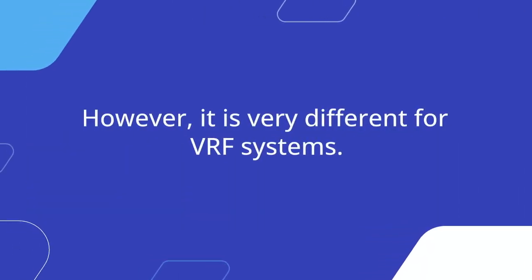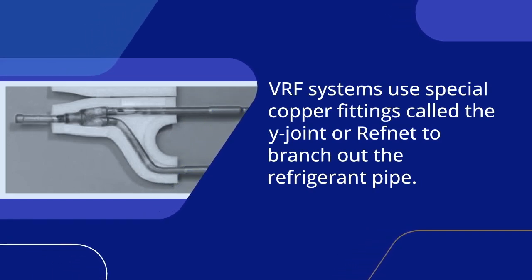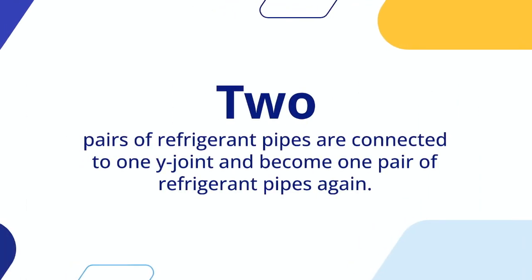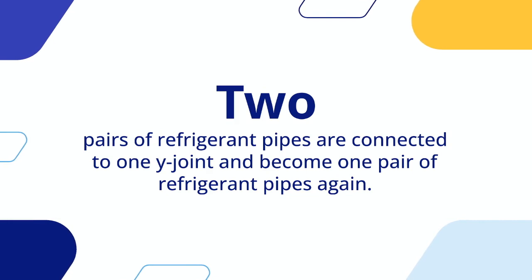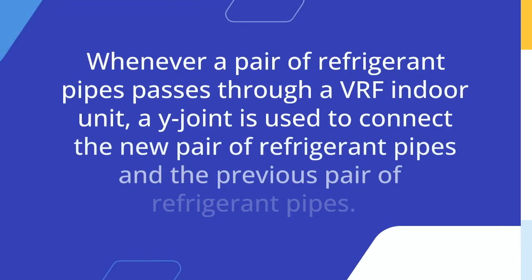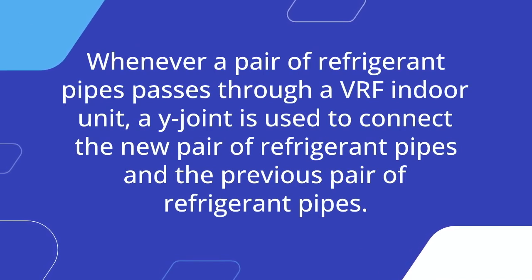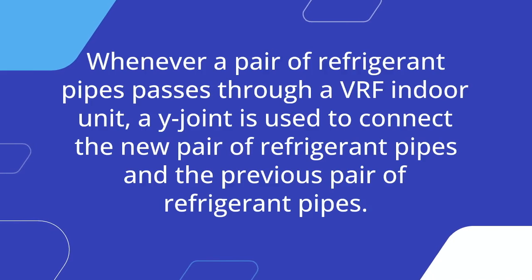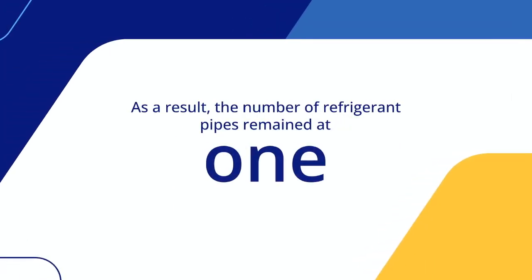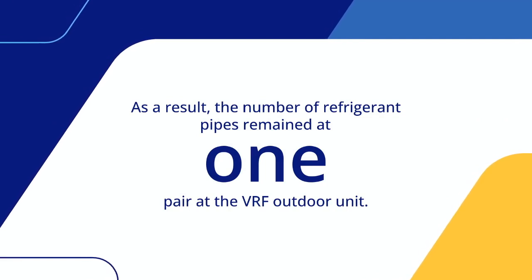It is very different for VRF systems. VRF systems use special copper fittings called the Y-joint or refnet to branch out the refrigerant pipe. Two pairs of refrigerant pipes are connected to one Y-joint and become one pair of refrigerant pipes again. Whenever a pair of refrigerant pipes passes through a VRF indoor unit, a Y-joint is used to connect the new pair of refrigerant pipes and the previous pair of refrigerant pipes. As a result, the number of refrigerant pipes remains at one pair at the VRF outdoor unit.